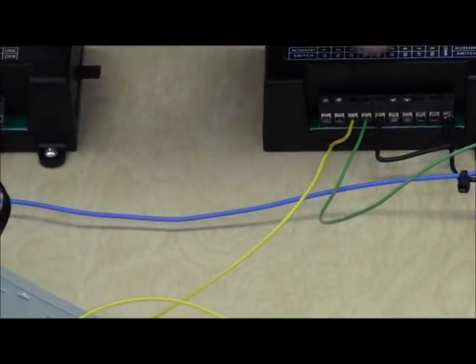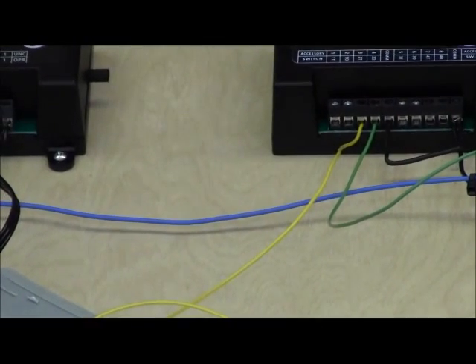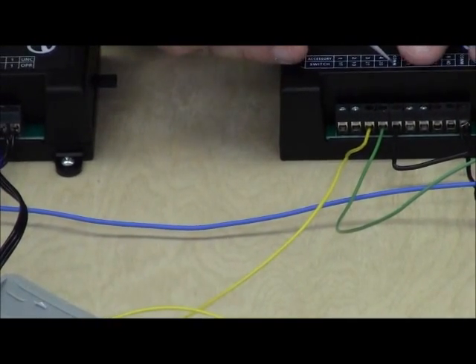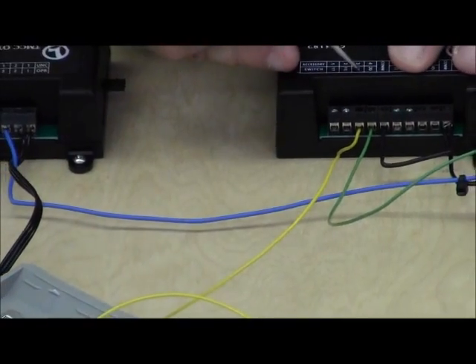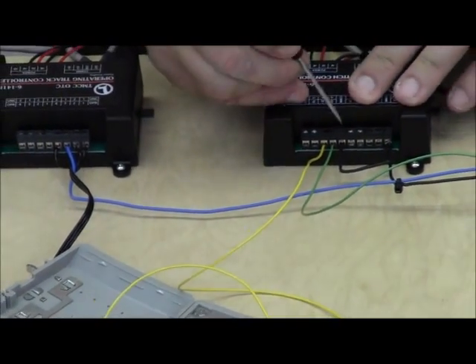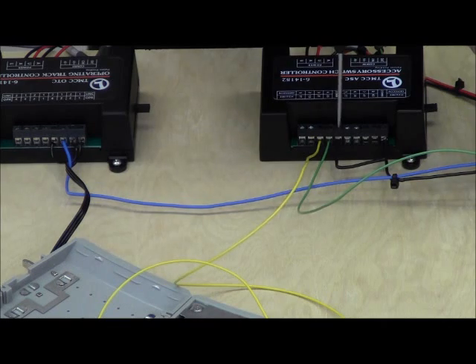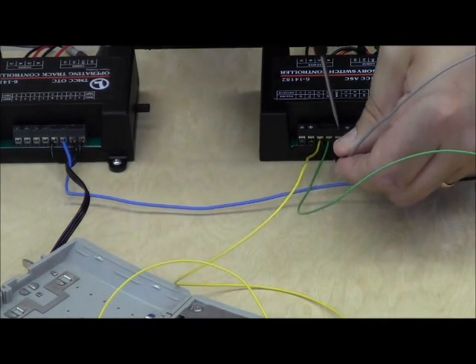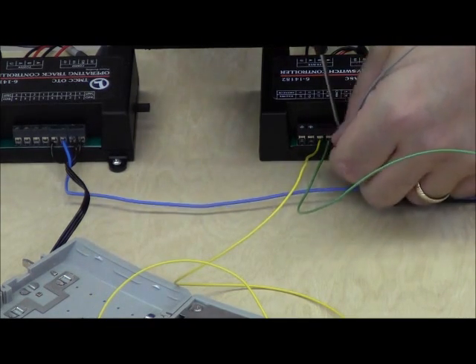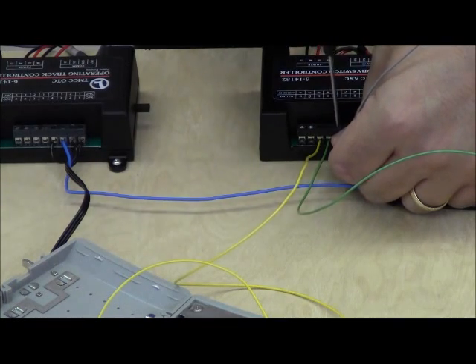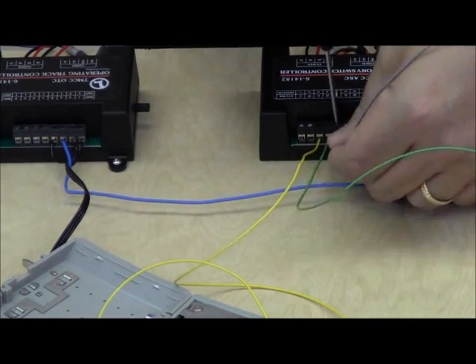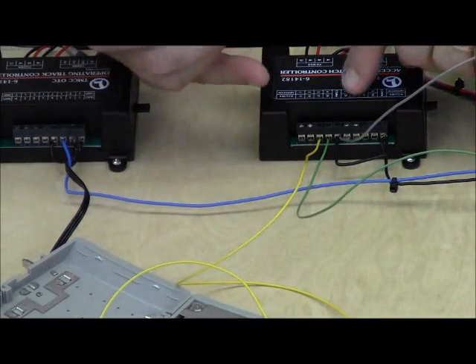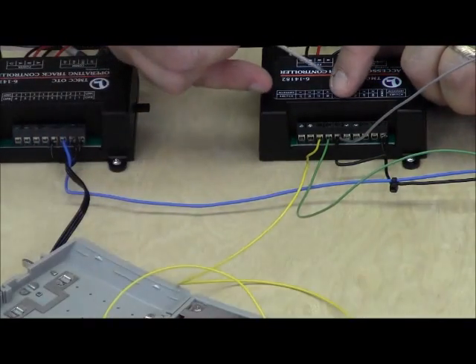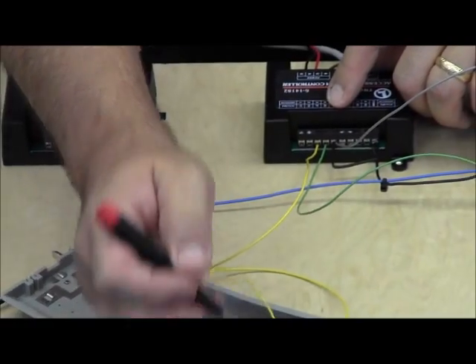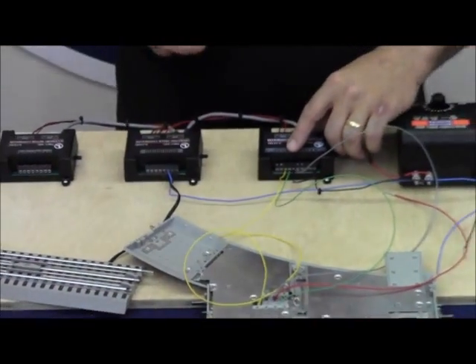Our gray wire, currently in ground, needs to connect to the common on our ASC, specifically the common that correlates with 2O, 2T, 1O, and 1T. Since we have a jumper, we'll just pop this terminal up and insert the gray wire. Now we have COM to ground, 2O to the out position, and 2T to the through position.